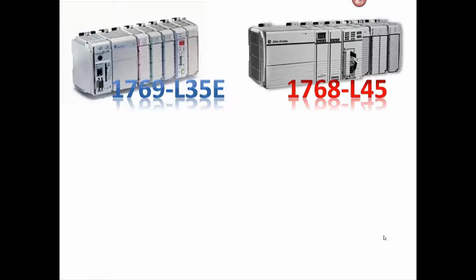Now the L45, which is on your right, begins with a power supply, a 1768 power supply. So if you're buying this stuff on the network, make sure you pay attention to what you're doing, because the power supply for the 1769 on the left will not work with the L45 or the L43.